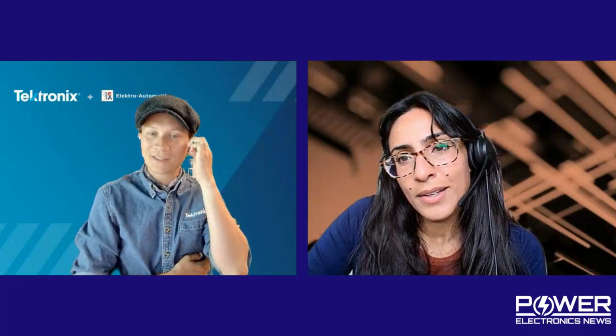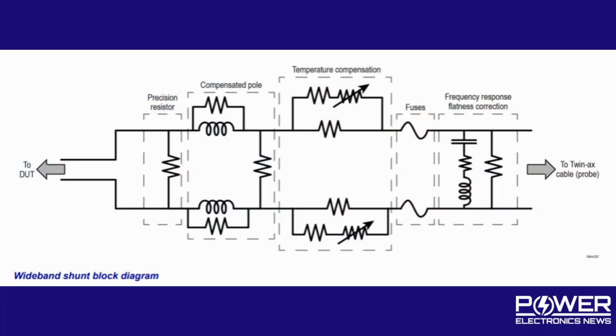The lower the resistance, the harder this becomes. The bandwidth of the shunt itself is directly correlated with the shunt resistance, so for the 5 milliohm shunt it required very fine tuning of this compensation circuit. There are actually two layers of compensation circuits built into the shunt itself.